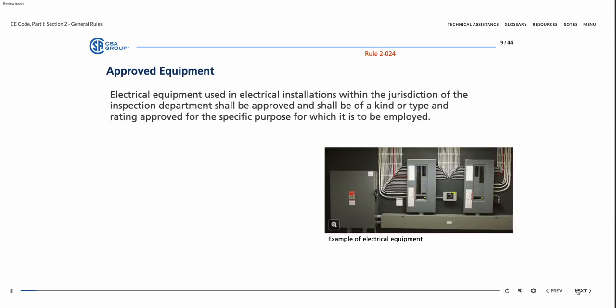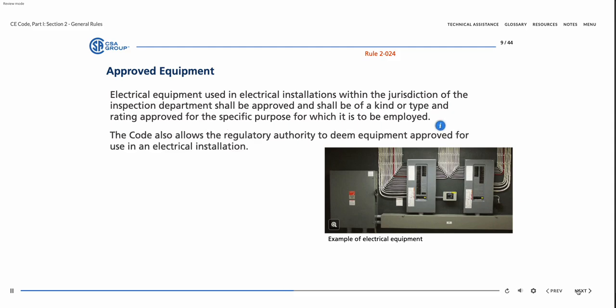Rule 2-024 covers approved electrical equipment that has been certified by an organization which is accredited by the Standards Council of Canada to meet the requirements outlined in CSA standards. The approved electrical equipment may also be covered in other standards that have been developed by standards development organizations, which are also accredited by Standards Council of Canada, and other recognized documents, ORDs. In the case where CSA group standards do not exist or are not applicable, other recognized documents can only be used where they correlate with the provisions in the CE Code Part 1 and do not create duplication with the standards listed in Appendix A. The code also allows the regulatory authority to deem equipment approved for use in an electrical installation.